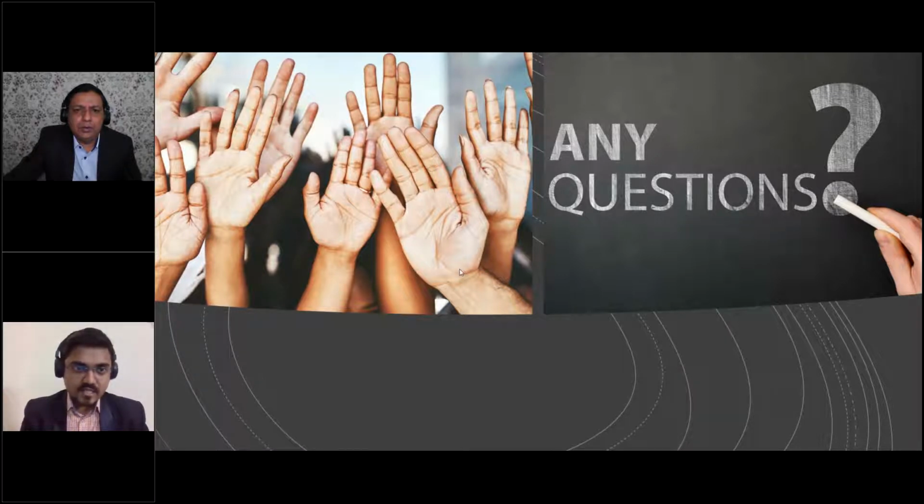Fatima is asking, do we need to have a separate CER for Australia submission, or can we use the MDR CERs with minor modifications? To answer Fatima's question, yes, you need to have a separate CER. If you are doing any minor modification, it cannot be a next revision of your existing CER.